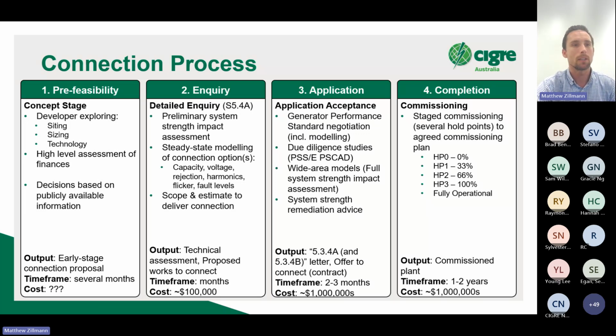Normally it's across 3 or 4 hold points. The first hold point is effectively a 0% release of capacity. You might ask why have a 0% release, but that's effectively just energization of the plant—often taking background power quality readings and collecting information before the generator starts, and sometimes energizing the inverters or system as part of preliminary testing and commissioning.